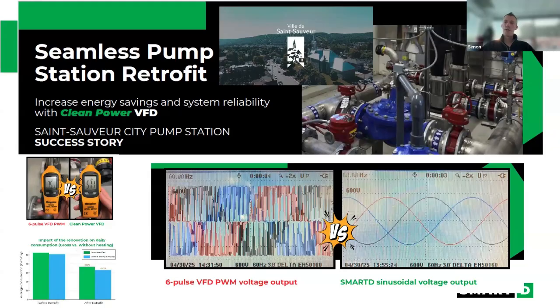And this is something that very often people will tell us when they first start up the clean power VFD: are you sure your drive is working? I can't hear the motor. But really, that is the element you are perceiving of the silent damage that's ongoing in your motor. In the meantime, in this case study, let me mention also that this is great. We deliver silence, we deliver clean sine waves, but we also deliver the efficiency you're expecting out of a retrofit. So you really have the opportunity to retrofit more easily and get that full ROI without the complication.